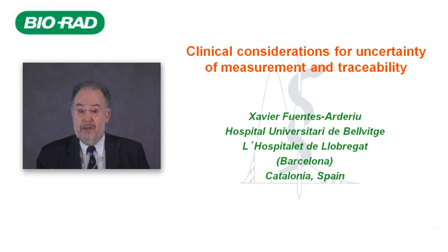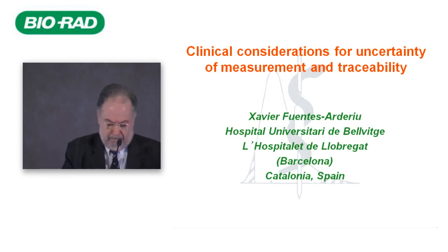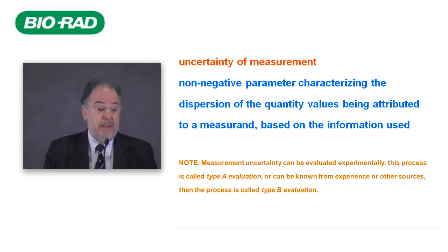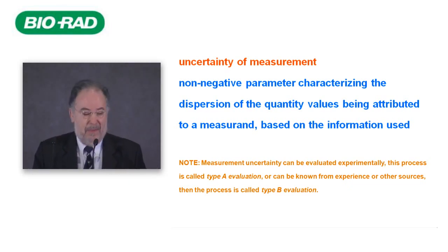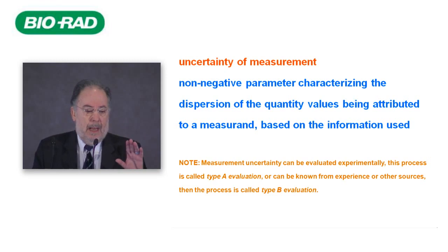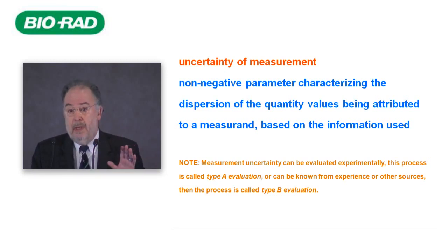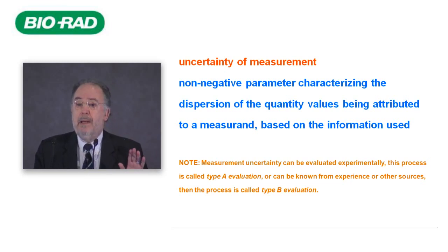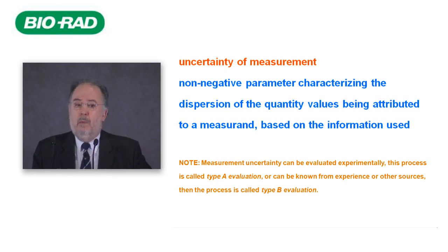The first concept is measurement uncertainty, or uncertainty of measurement. This is a statistical definition. The important thing is that uncertainty is, in most cases, a standard deviation — this is a very basic concept. As a standard deviation, we can estimate it by an experimental procedure; this is the Type A evaluation of uncertainty.